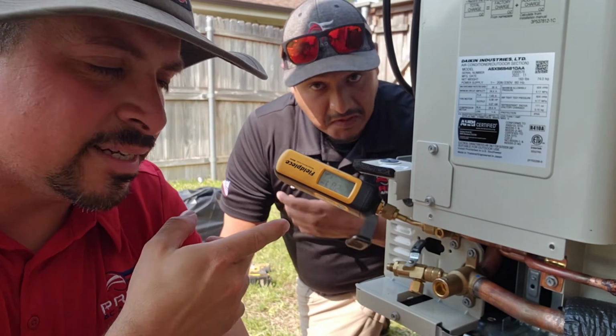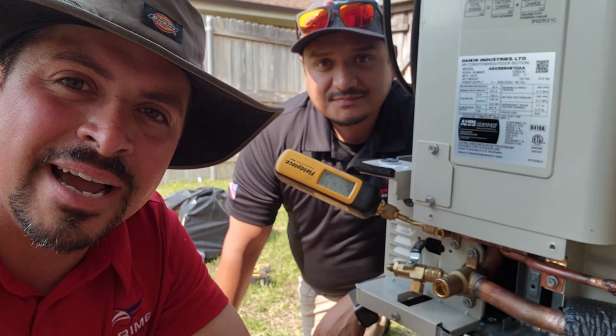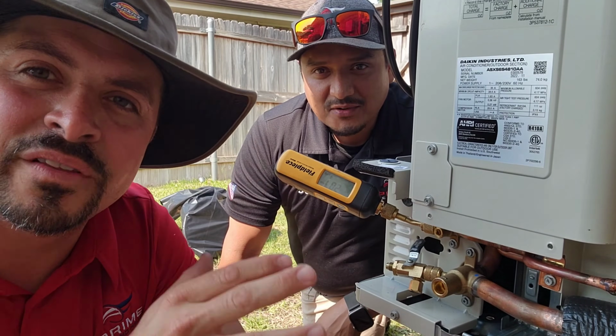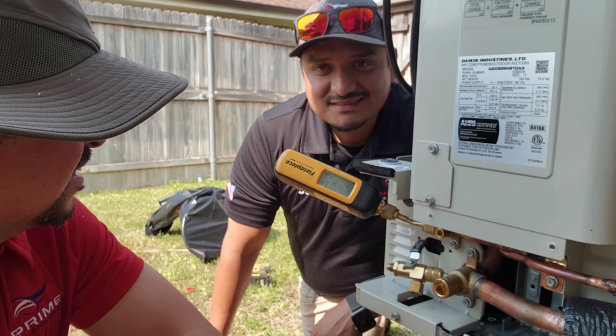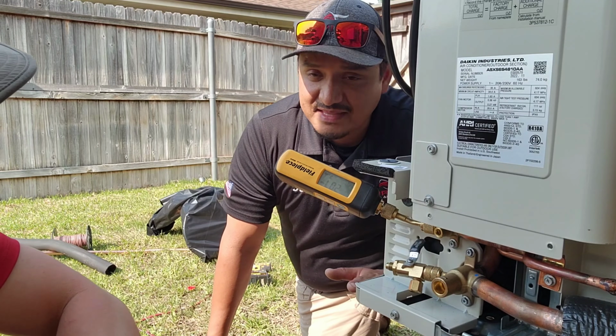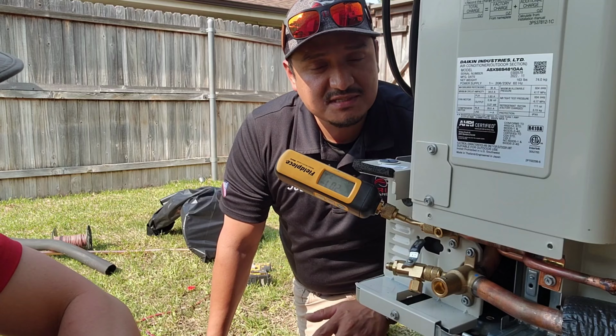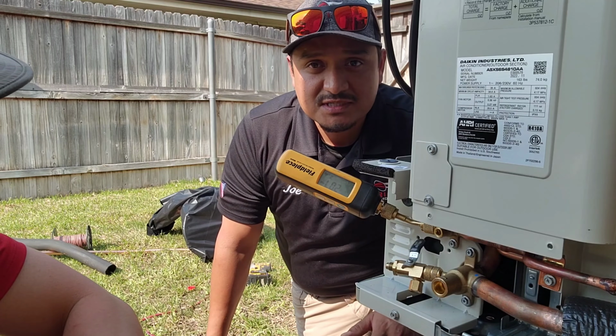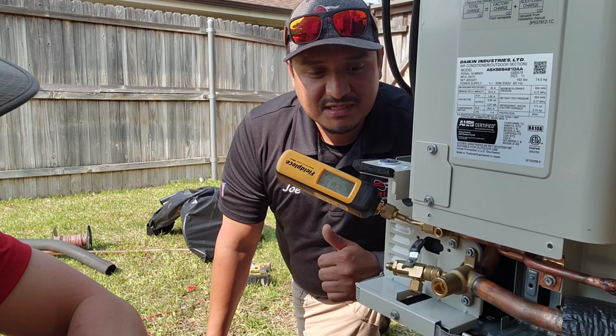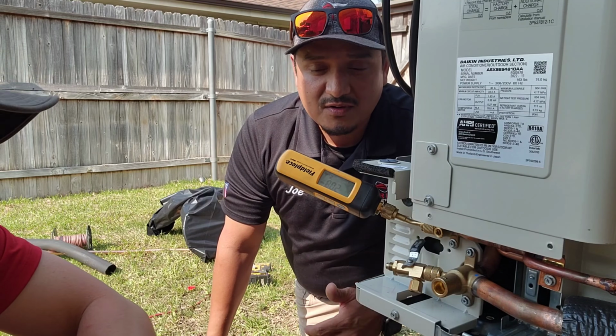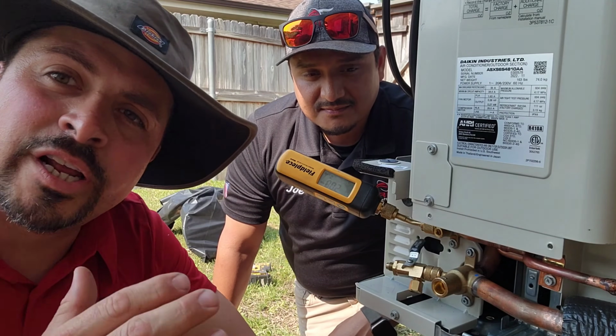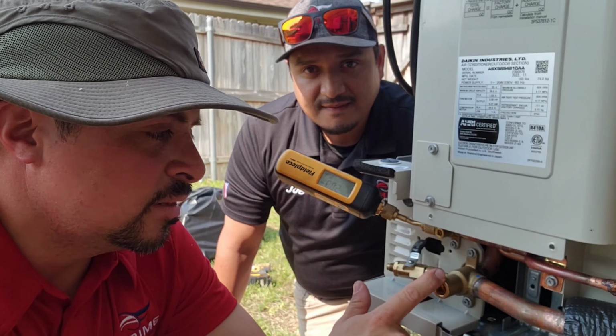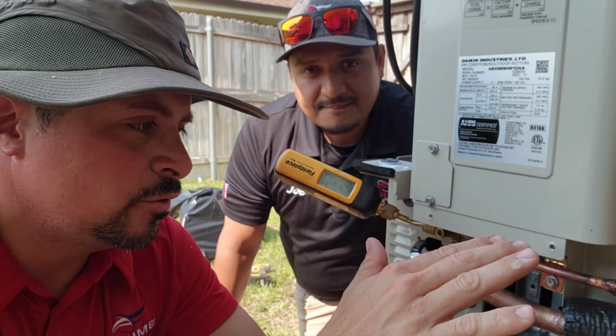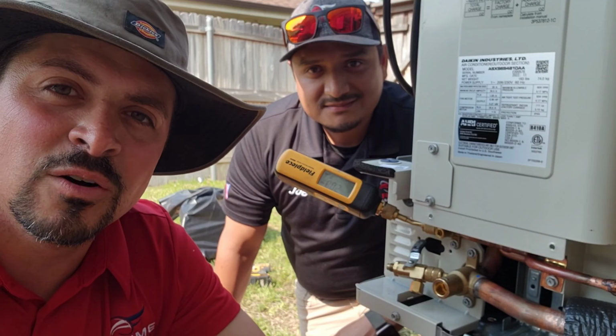Okay, so we made it to 207 microns, far exceeding what the manufacturer calls for. That ensures there are no impurities, no moisture, no oils in there. Everything's nice and clear, ensuring this unit is going to perform well for years to come. Now we're going to open up the valves, allow the refrigerant to flow, and continue on with the installation.